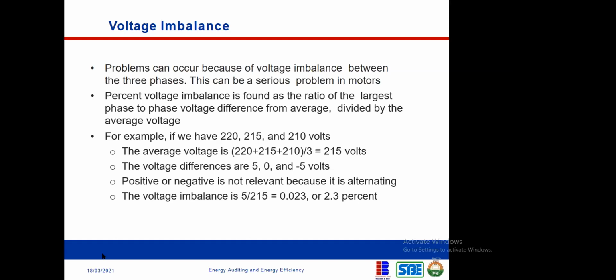First of all, you need to determine the average voltage of the three phases. So you need to determine the average of 220, 215, and 210. When you add all of them and divide by 3, you have an average voltage of 215. Now the voltage differences are, for the first one, 5, which is 220 minus 215. The second line, you have 0, which is 215 minus 215. Now the third line, you have minus 5, which is 210 minus 215.